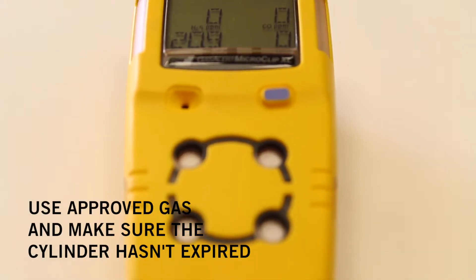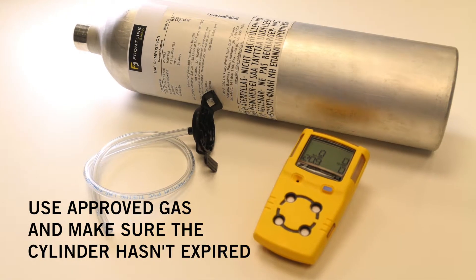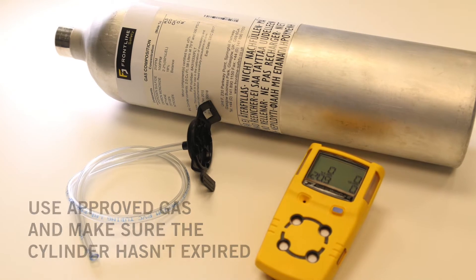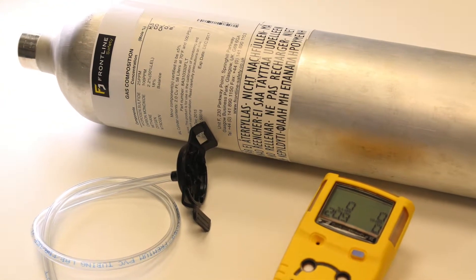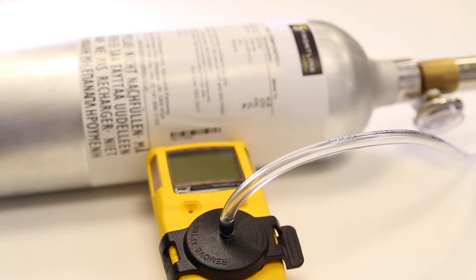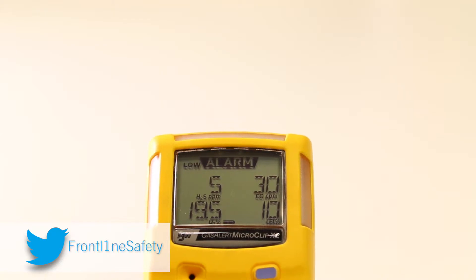Before bump testing, ensure you're using an approved gas and that the cylinder is not past its expiration date. Most manufacturers recommend that your gas monitor should be bumped daily, but make yourself aware of any site-specific or company-specific procedures around bump testing.